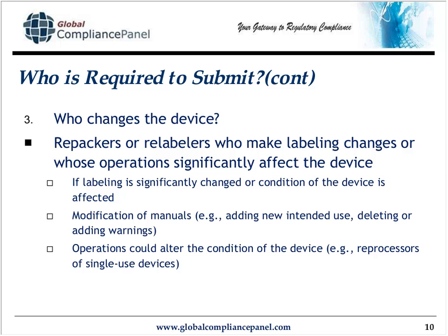If they're modifying the manuals, maybe they're adding a new intended use, and we'll talk a little about intended use in a little while. If they're deleting or adding warnings, or their operations could alter the condition of the device. There are, in some cases, medical facilities such as hospitals. However, there are private firms out there that reprocess single-use devices and then resell them. These firms are significantly changing a device enough that they do need to submit a 510K.